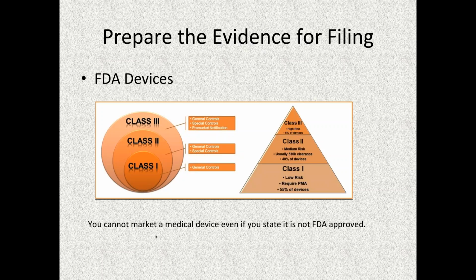Preparing the evidence for filing. For those of you who have not been exposed to the FDA, there are two main classifications in the FDA: devices and drugs. There are some subsets to that which are now being more accepted. However, the FDA has not completed all of their guidance documents, but the subsets are de novo devices and combination devices. But within the two umbrellas, drugs or devices, if you're not sure what that is, there's a submission which we call the 513(g) that you can submit to the FDA, asking them to look at your product and decide for you whether it's a drug or device.